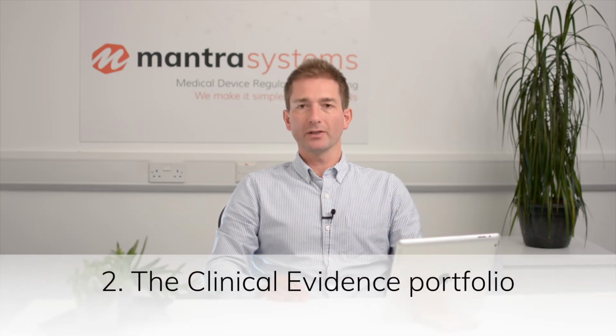Ensuring adherence to these standards from the earliest possible stage will mean that the device itself is more likely to be accepted. The second domain was clinical evidence, and it's vital to not underestimate just how important clinical evidence is under the MDR. The message is to start planning as early as possible. All devices will need a clinical evidence portfolio, and to an extent that's even true if you have a legacy device that's been approved for a long time under the MDD. For new devices, it's important to allocate resources and plan around clinical evidence requirements from the earliest possible stage. Remember the old adage that it takes 4 years to produce 3-year data.